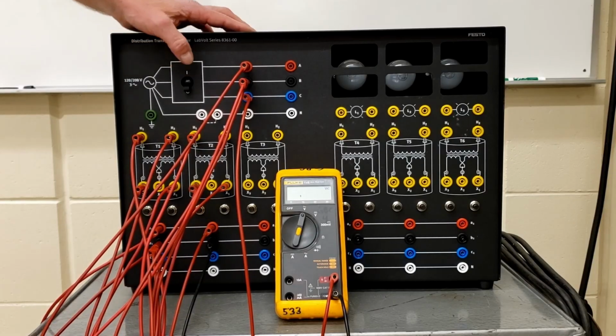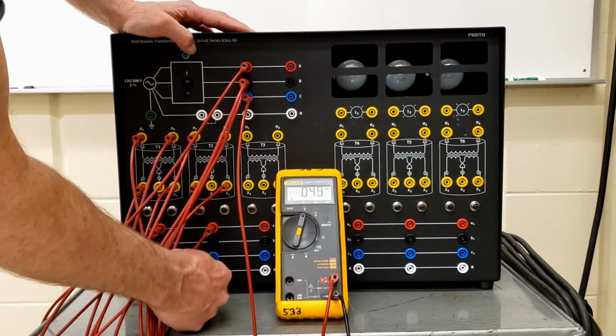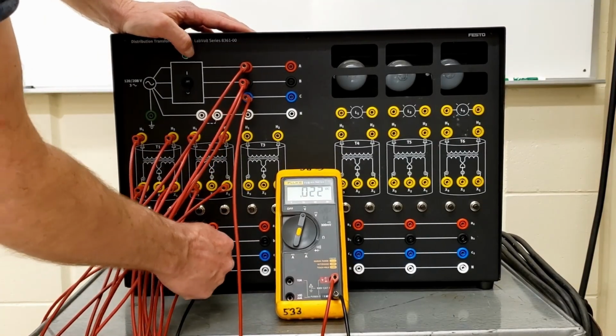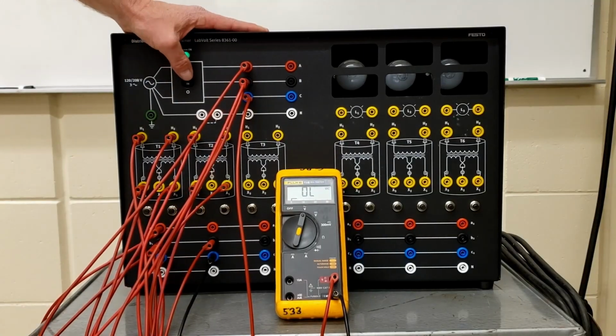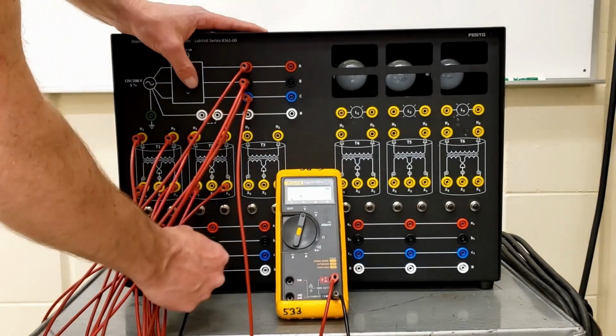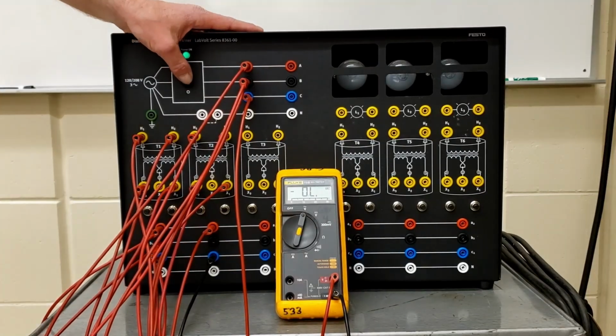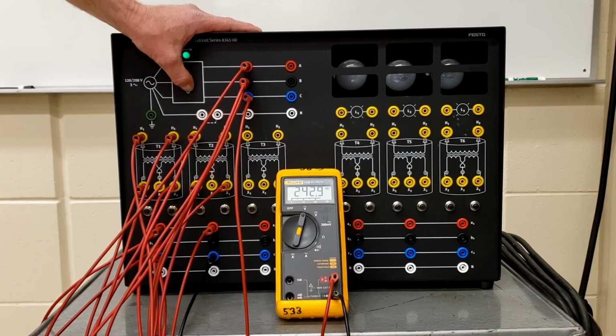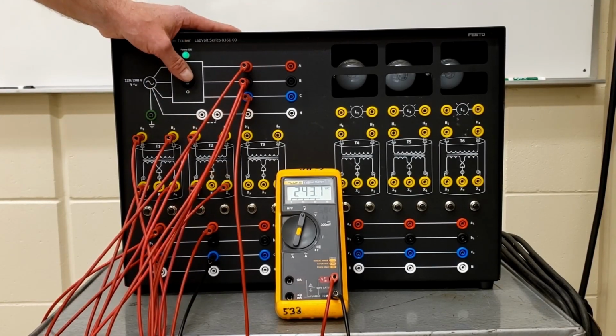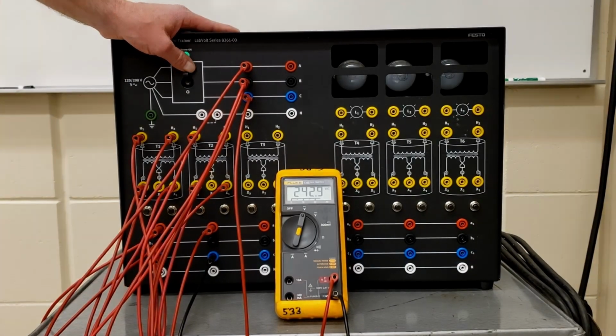Okay, between B and C should be an identical 240. Yes. And then between C and A, we should have 240 volts as well. Very nice. Okay, so the open delta is awesome in that you can use two single-phase transformers to create a three-phase bank. Like we clearly have three separate voltages that are outputting from two transformers.